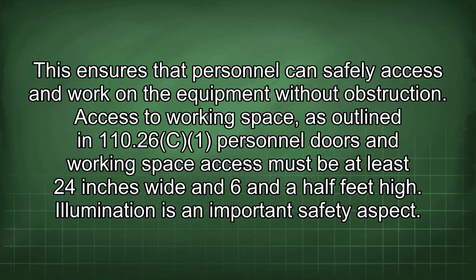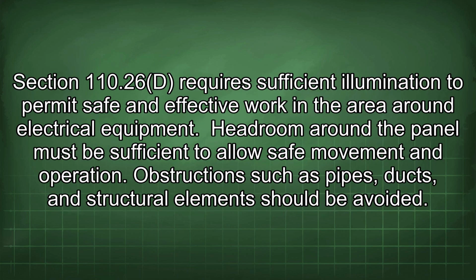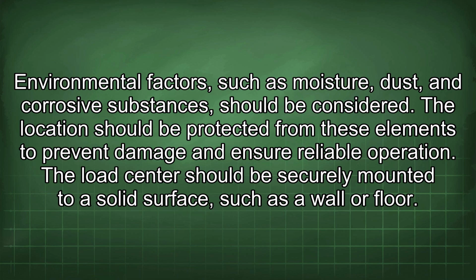Illumination is an important safety aspect. Section 110.26(D) requires sufficient illumination to permit safe and effective work in the area around electrical equipment. Headroom around the panel must be sufficient to allow safe movement and operation. Obstructions such as pipes, ducts, and structural elements should be avoided. Environmental factors such as moisture, dust, and corrosive substances should be considered. The location should be protected from these elements to prevent damage and ensure reliable operation.